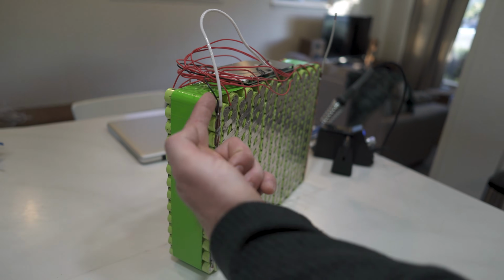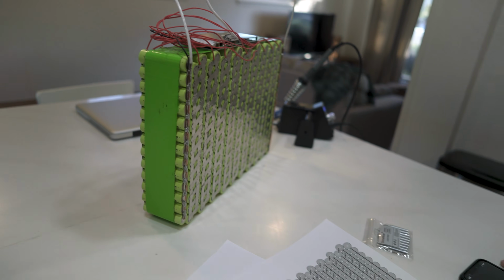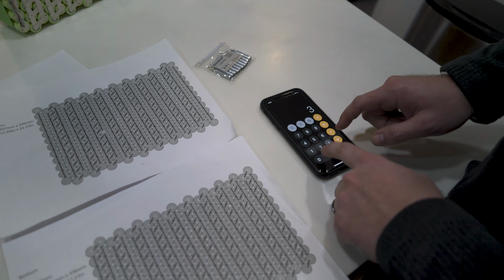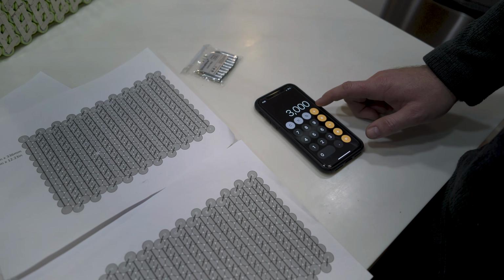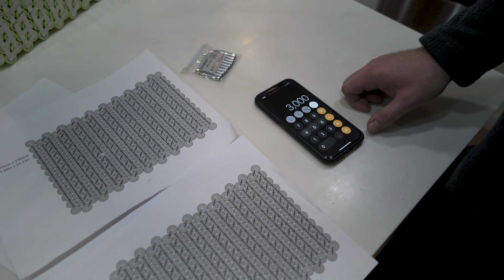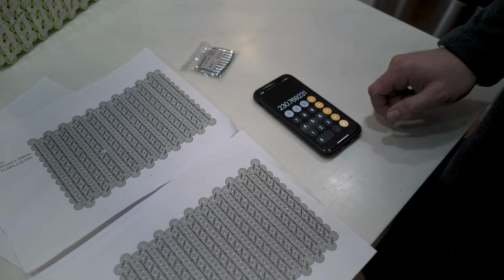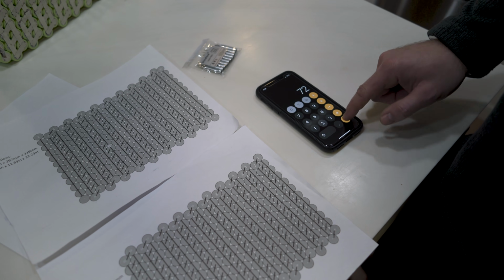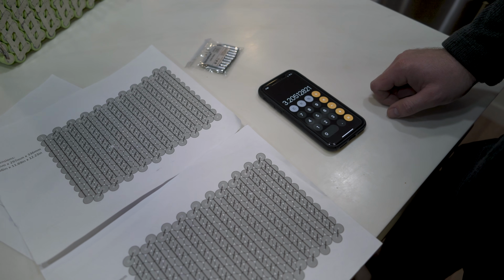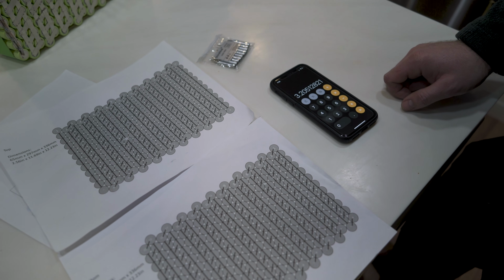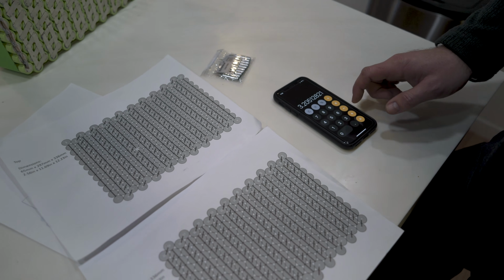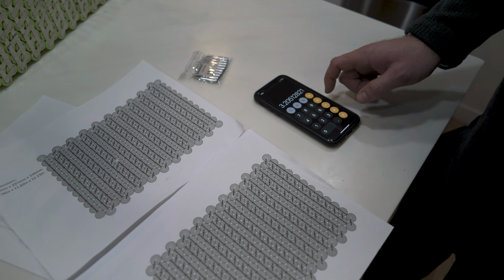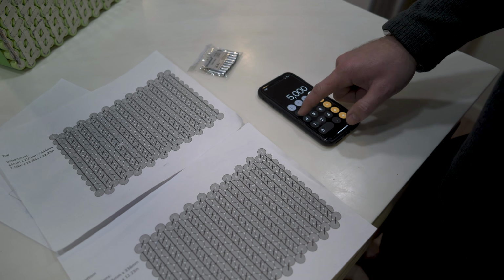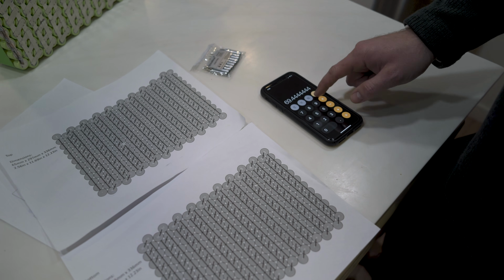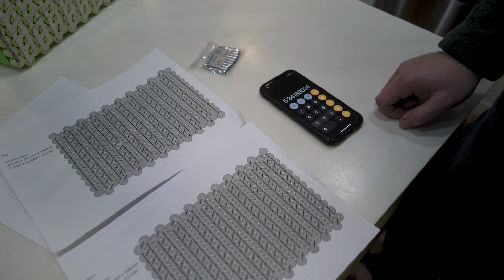As it sits, the run we've devised, if it's pulling 3,000 watts on the current motor, and we have 13 in parallel, divided by the 72 volts, each cell is only asked to pull 3.2 amps, which is not a ton. If you were to up this to a 5,000 watt motor, divide that by 72 to get the amps, then divide by 13 — still reasonable.